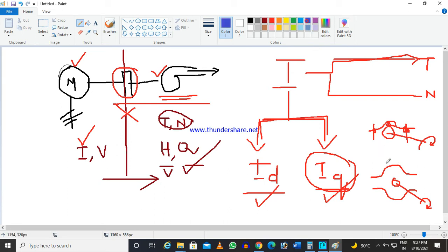One time it will hit here, and while going down it will hit here. So if your excitation is omega, and you put one accelerometer here or here, you will get a frequency of 2 omega. Anytime your mechanical response, the vibration or displacement, whatever you call it, is coming at double the excitation, it is commonly known as looseness.